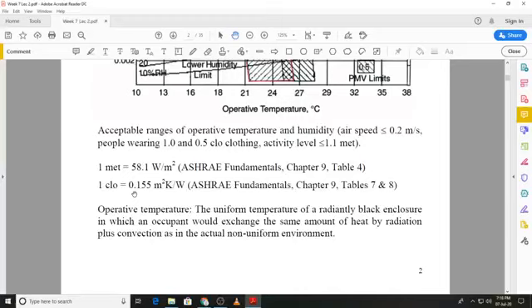If of course we deviate from these standard conditions at which Standard 55 has been obtained, if you refer to the ASHRAE handbook, you are given certain guidelines on how you can shift the conditions of the comfort zones. For example, what happens if the air speed changes, or if people are wearing clothing which has a clo value other than 1 or 0.5, or if the activity level is greater than 1.1. So there are certain recommendations for those, and if you are interested, you can refer to the ASHRAE Fundamentals Handbook to get a more detailed idea of how things would change when we deviate from these standard conditions.